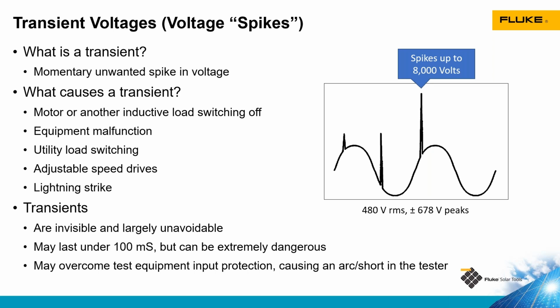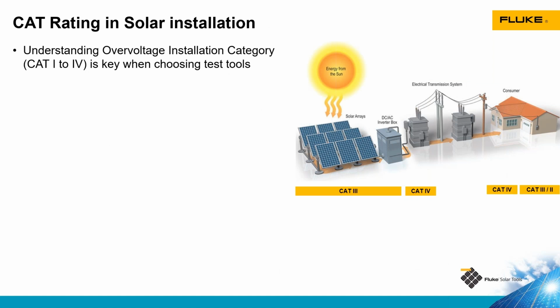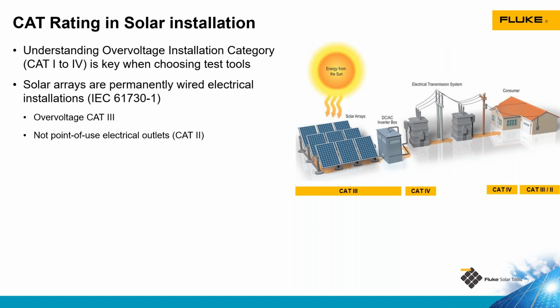The important thing is the last bullet on this slide, that if you have a piece of test equipment that is not properly rated, a transient voltage spike could overwhelm the tool. It could cause damage to the tool, and it may be a safety hazard to the person who happens to be holding the tool doing testing while the transient voltage spike happens. In order to deal with transient voltage possibilities, we have category ratings. Category relates to the environment in which you are doing the test. They range from category 1 to category 4. The higher the category number, the closer you are to the source of a potential voltage spike, and the higher the danger from that voltage spike.